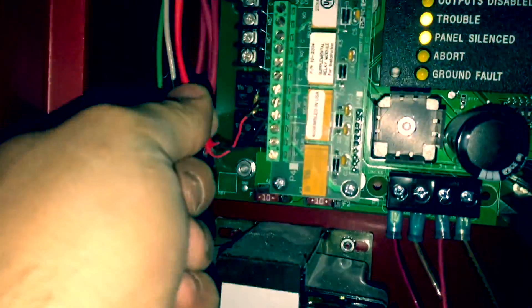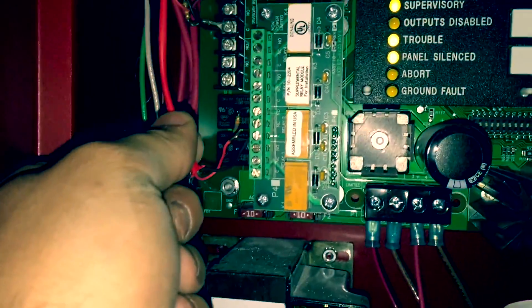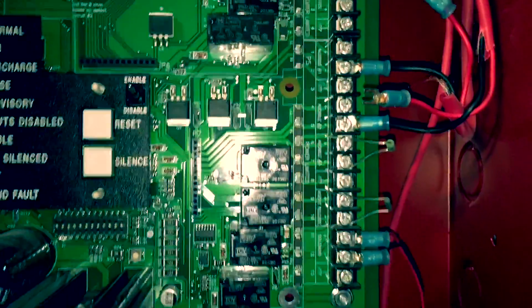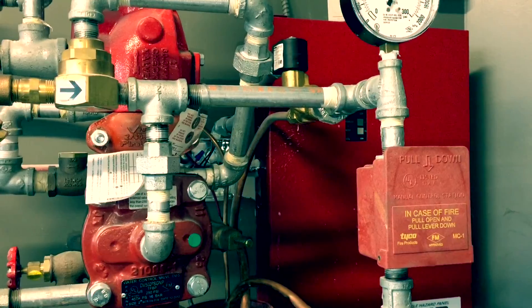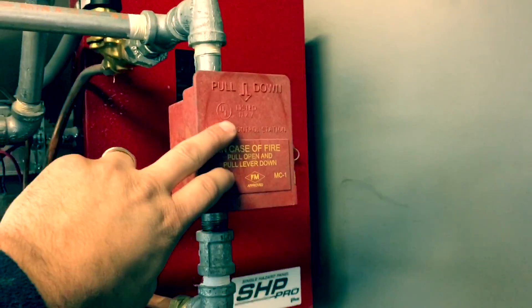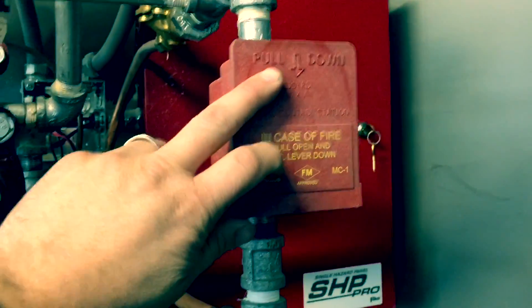Went to the panel inside, pulled the circuit there so the auto is off now. Got the system isolated and shut down, got the system on test. We're going to pull the manual pull to see if it works and if it activates the system. We're going to pull the pull station down to activate the system.